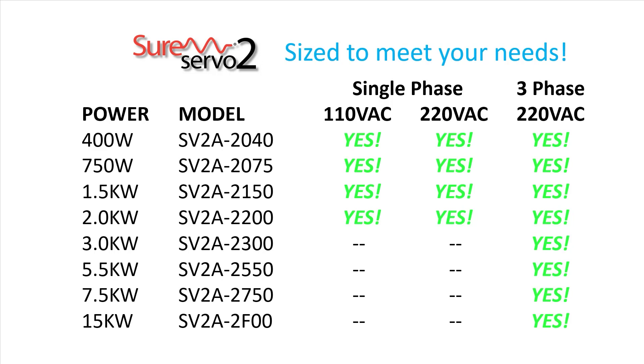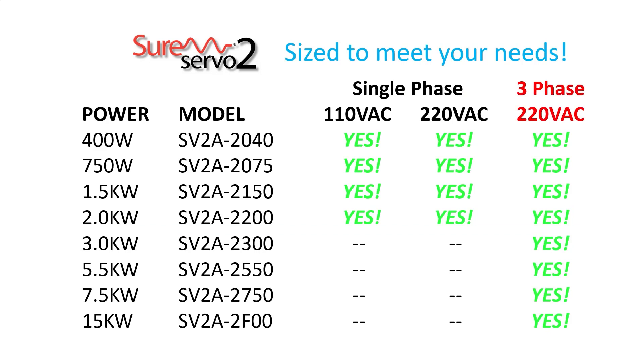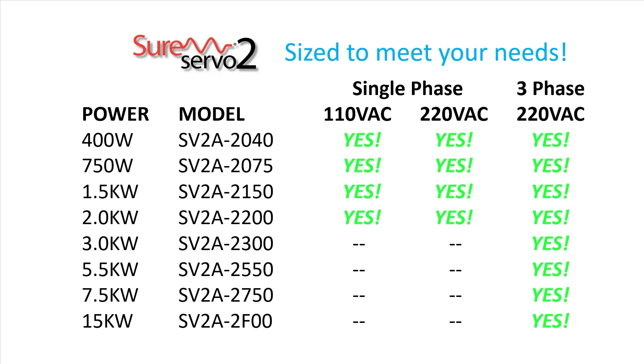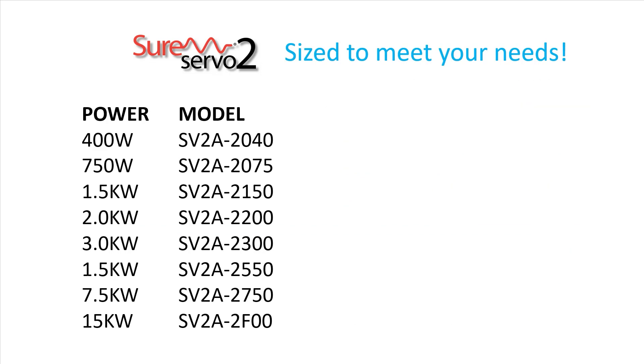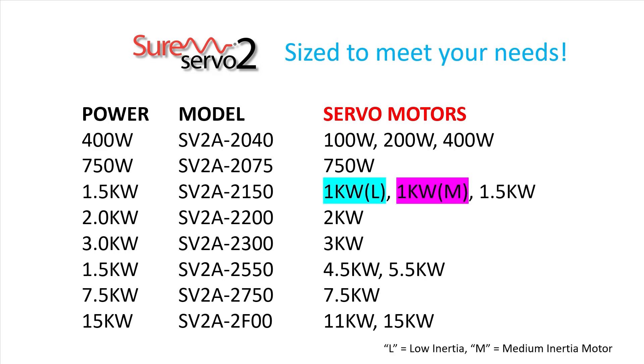The SureServo 2 drives run on single phase 110 or 220 through 2 kW with 3 phase 220 drives through 15 kW. And those drives work with an even wider range of motors starting at just 100 watts. And the 1 kW motor even has a low and a medium inertia version. All of which makes the SureServo 2 system ideal for your low to mid power servo applications.